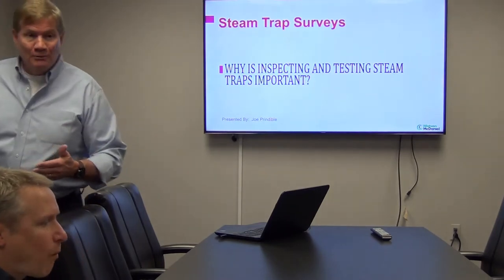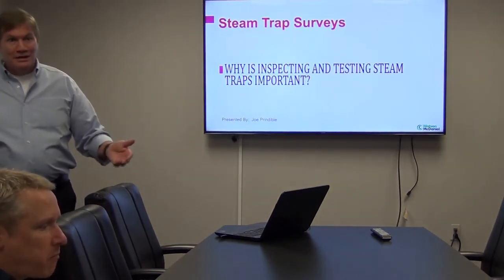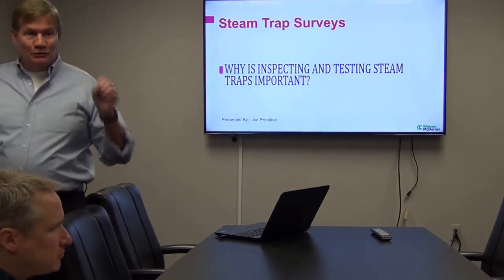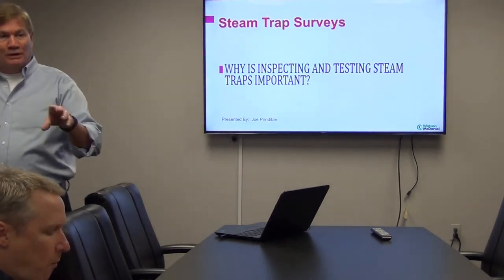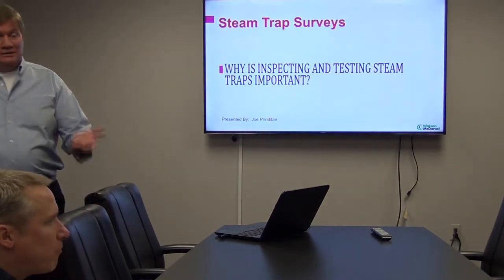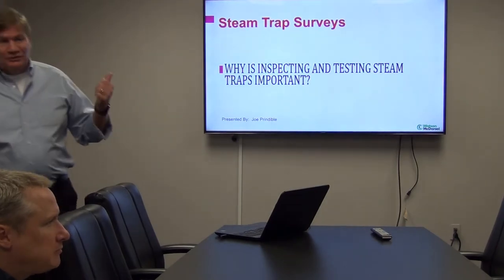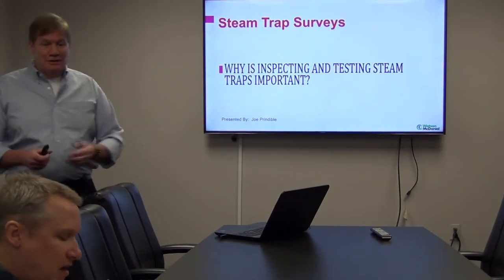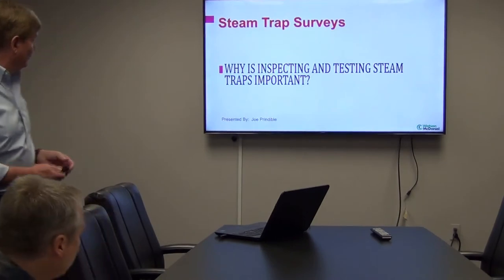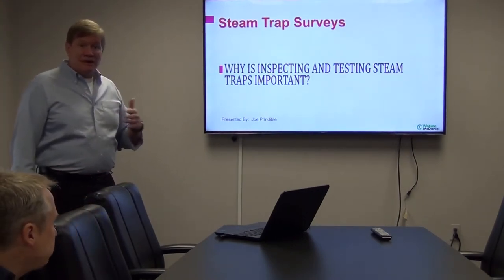Just like in your home, if you heard your toilet running, you'd think, I'm wasting a lot of money going down a drain. If a trap fails open, all it's doing is allowing live steam to flow right through, wasting money. Or if it doesn't want to turn back on, you're backing up into your equipment, which reduces the efficiency and operation of your system. So that's a big reason why we do trap testing.